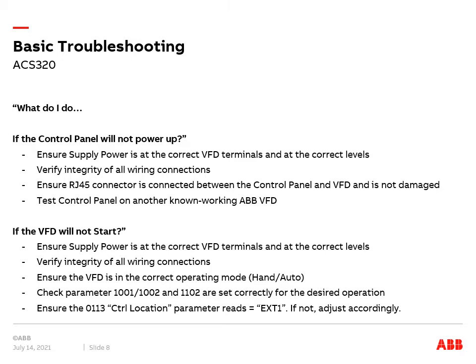You'll also want to ensure the VFD is in the correct operating mode, for instance hand or auto. Check parameters 1001, 1002, and 1102 and ensure they are set correctly for the desired operation. Ensure that parameter 0113 control location reads equal to ext1. If it does not, adjust accordingly.